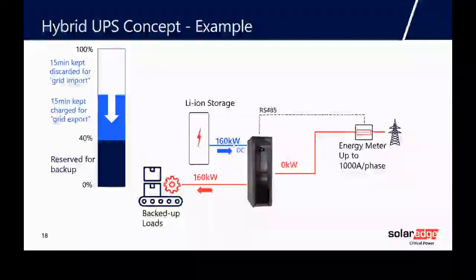So we would never, using this UPS system, dig into the critical power via software and controls—we would always keep within the window for grid services. So your client could be assured that although the UPS is being used, the power is always constant. One of the key benefits is the customer gets good payback for having these functions.